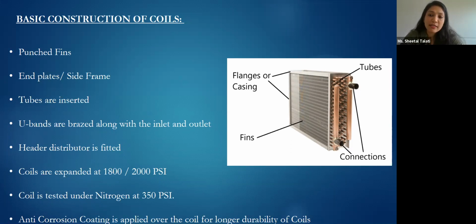The coils are further expanded to 1800 to 2000 psi so that there is a bonding between aluminum and copper for heat transfer. And finally, the last stage is testing of the coil. The coil is flushed. If it's hydro expanded, the water needs to be flushed out of the coils. And the coil is tested under nitrogen at 350 psi. Anti-corrosion coats are also applied over the coils to increase the durability and the life of the coil.